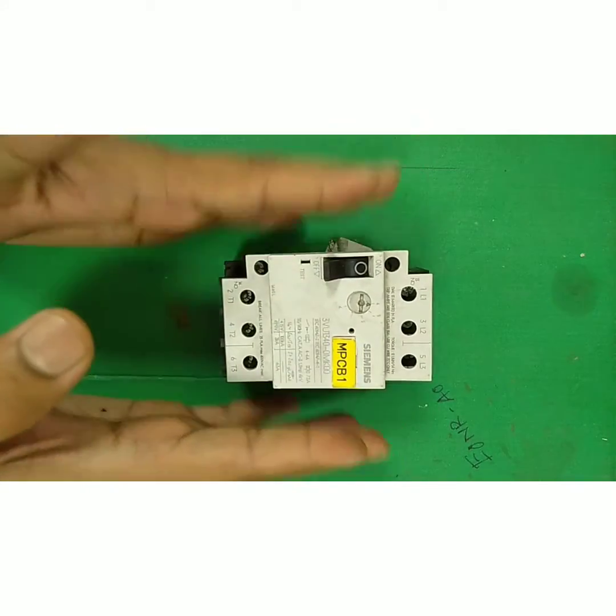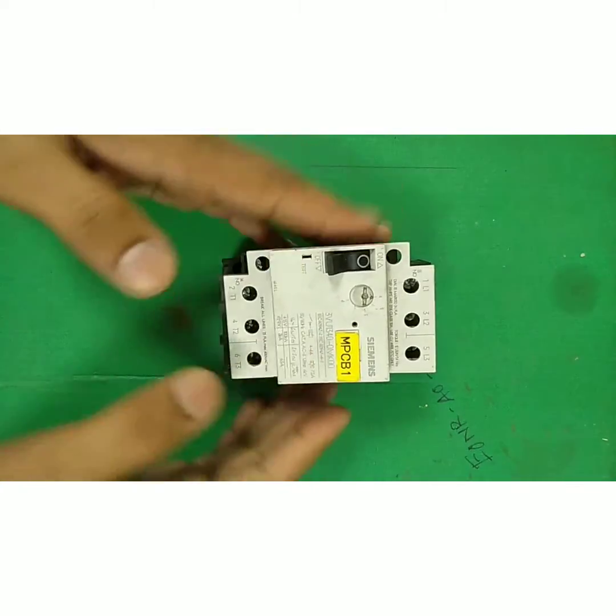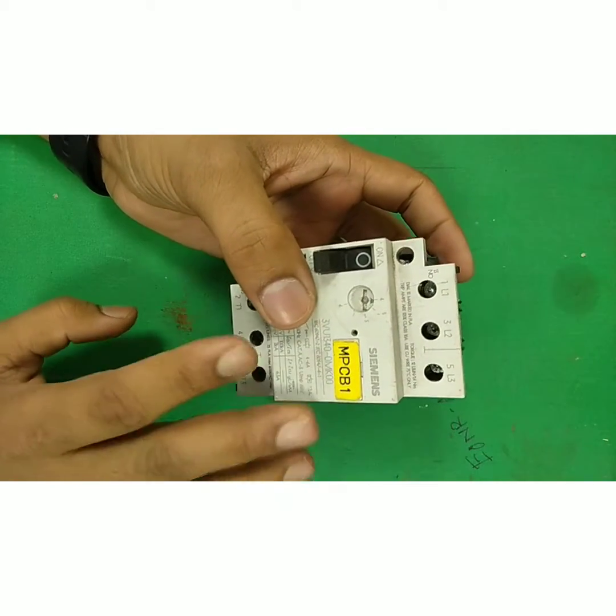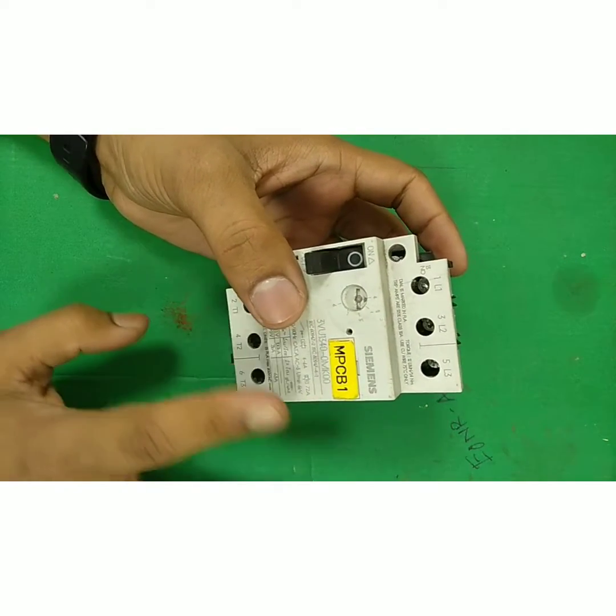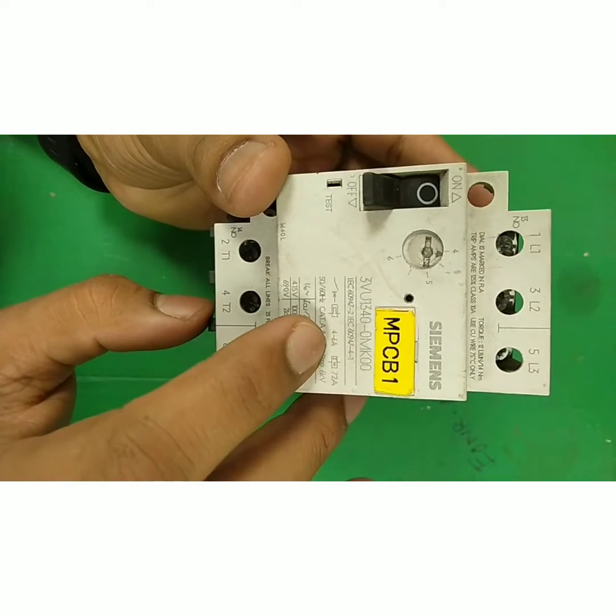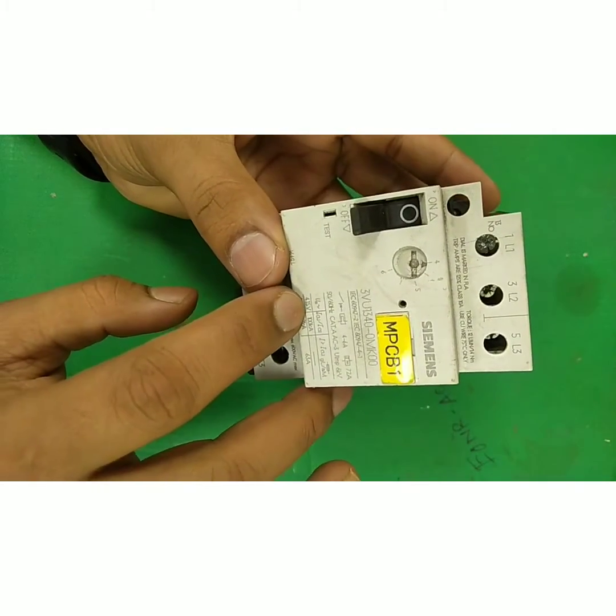First of all, we have to see some specifications of this MPCB. This MPCB has a range of 4 to 6 Amps, and its insulated voltage range is 690V maximum. The rated voltage is 415V, so we can operate it on 3-phase 415V. Here is the incoming, and RYB are the outgoing terminals.